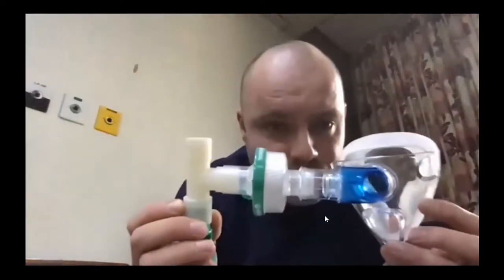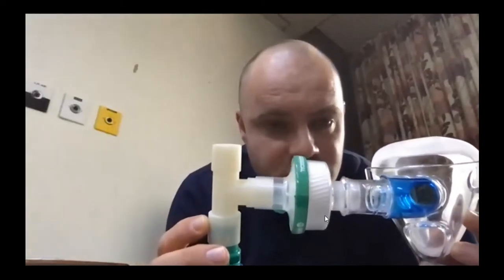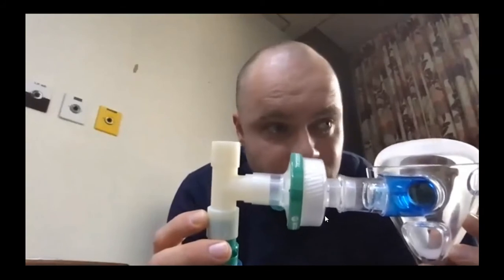Yeah, sure. So, the one problem with humidification, I think, is that all our flow is going to be the vast majority unidirectional down these circuits. So I think in this configuration, I don't think that HMEs will help much. I think if we're going to get a lot of humidification, we either need to look at water bath humidifiers, or possibly we could do something with nebulization, saline nebulization or water nebulization. But yeah, in CPAP configuration, I'm not sure how crucial humidification is, as the London guys' experience was. Yeah, so in the single port mask, your flow is bidirectional across your HME, so you do retain the moisture, as we would with HME use anywhere else.